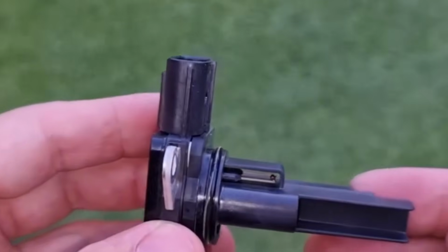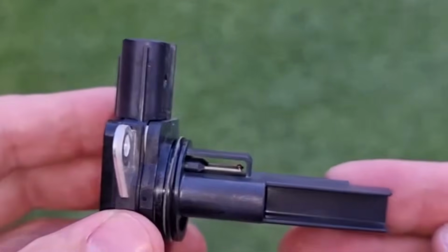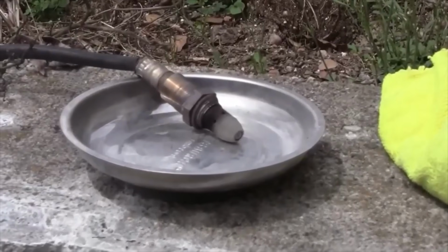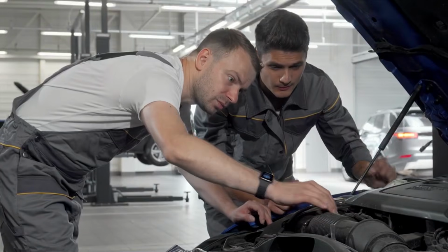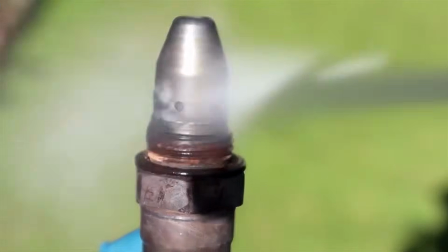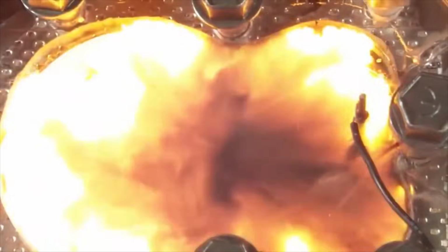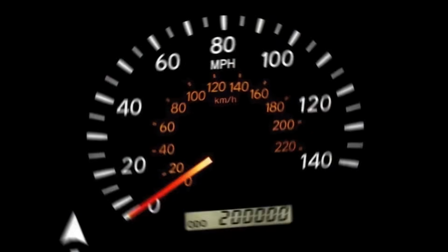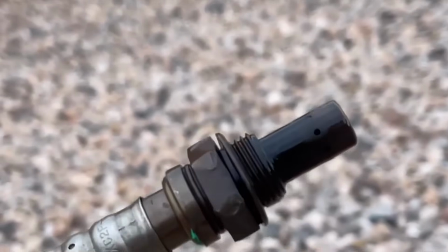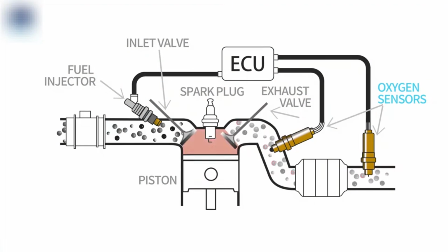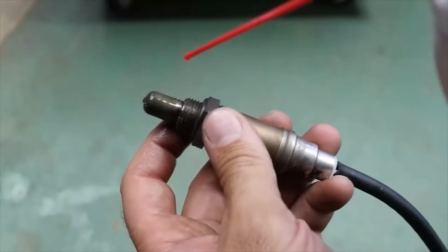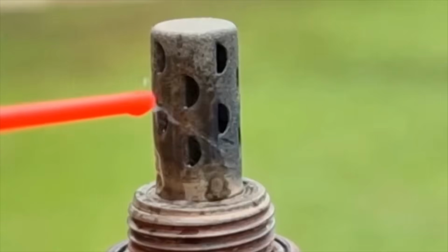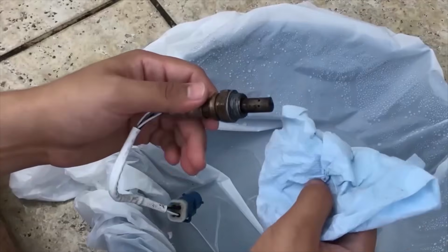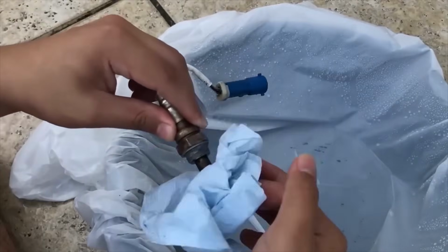The protocol is simple. Submerge the sensor tip in your warm, soapy water. Gently agitate it every 5 minutes. Don't scrub, don't brush, just gentle movement. I pushed it further. Tested 45-minute soaks, 60-minute soaks, diminishing returns after 30 minutes. You're not getting cleaner, just wasting time. 30 minutes is the sweet spot. Set a timer. Walk away. Let chemistry do the work instead of forcing it with chemicals and elbow grease.